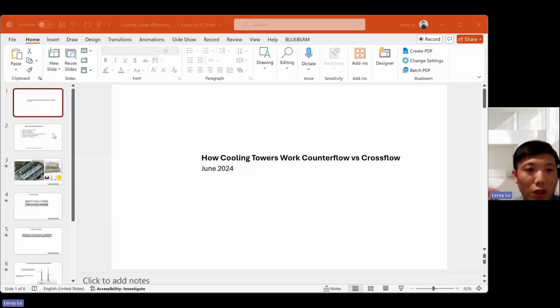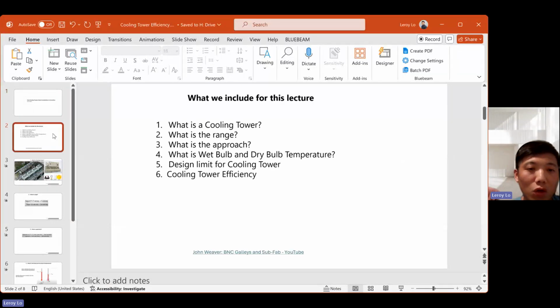The main topic is cooling tower efficiency. Let's move on to what we'll include in these lectures. So, what is a cooling tower? That will be a quick recap. Then, what is a range, and what is an approach? Number three, number four, what are wet bulb and dry bulb temperatures, and then what is the design limit for cooling towers. And finally, we'll go to the calculations, which is the cooling tower efficiency.